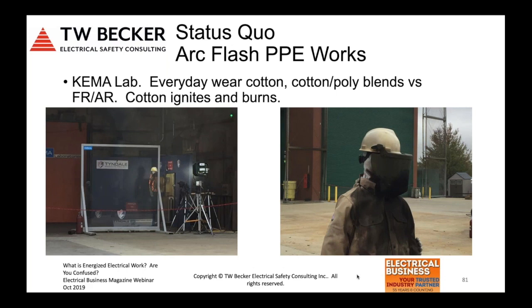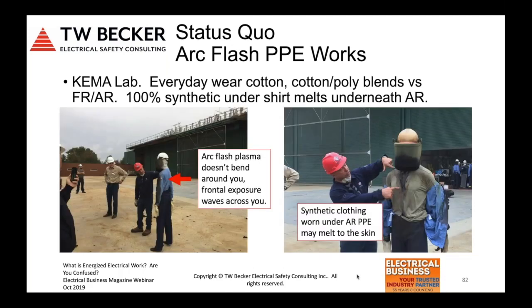I was actually at the Kinectrics lab last week and witnessed arc flashes of clothing. The PPE works if it's actually arc rated and if we ensure that we don't have 100% synthetic or cotton polyester blends underneath, because that clothing will melt. So on the left, the slide will show you that as well. When we get this arc flash, it's a wave. The instant energy is a wave. You can see the back of that arc rated shirt wasn't impacted.